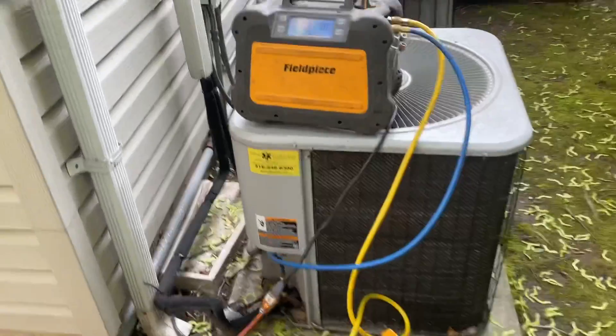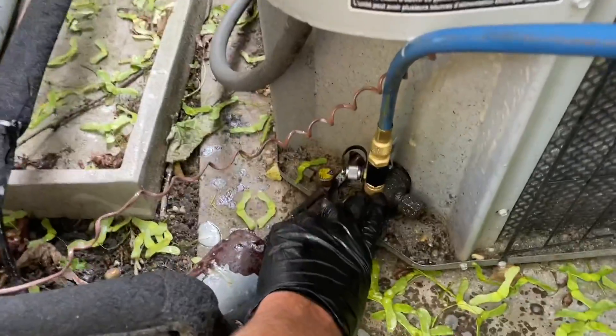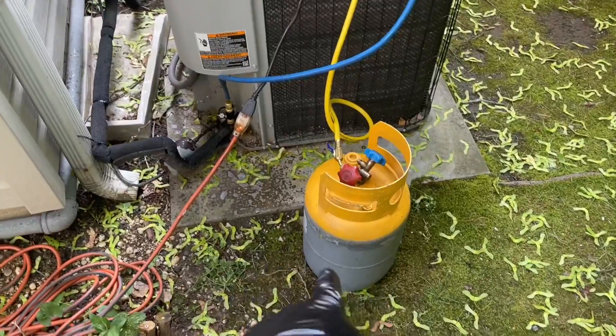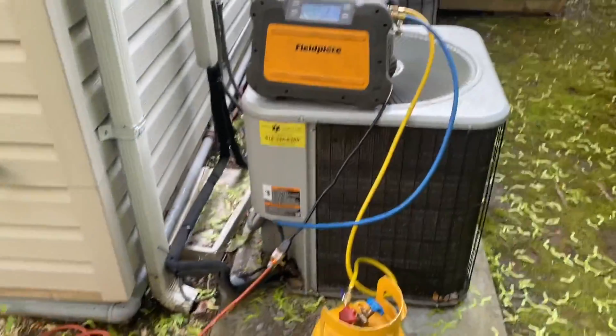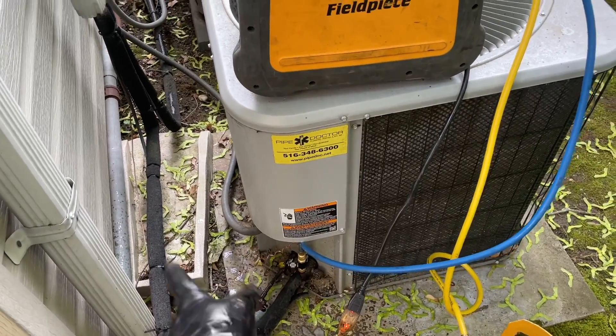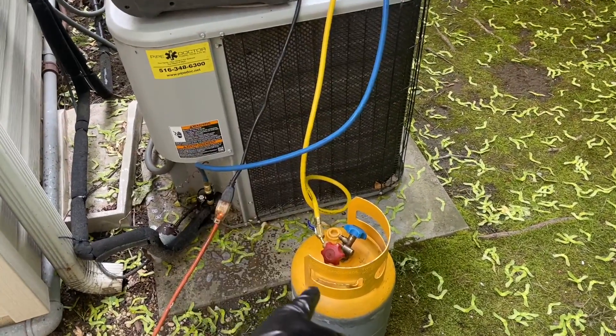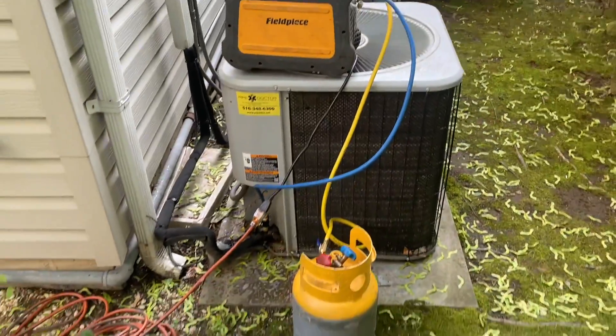We're getting started outside. I've got my Fieldpiece recovery machine. I took out the Schrader core out of the suction side, and right now we're pumping down the system. I could also weigh out the charge, but I'm good with that this way. I can also use a manifold and hook up both ports, high and low side, going to the manifold, to the recovery machine, to the recovery cylinder. It's 7:35 in the morning. Let's get this done. Let's head up to the attic.